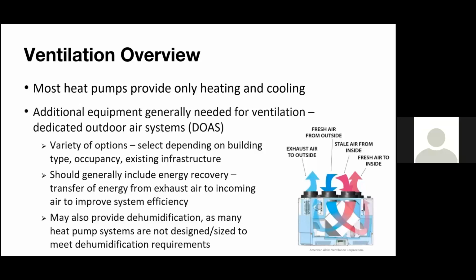So the second option, probably the first option, we'll forget about what I just mentioned there, is using an ERV with a static core. If you want some kind of energy transfer, you don't want to waste the heat that you put into a building, what you're able to do is bring in your outside air and mix it with your return air. So you could have 70 degrees as your return air. Let's just say worst case scenario, it's 0 degrees in Boston. We're mixing that together and you might get 35 to 40 degrees, right? And maybe if you did a little mixed air and brought that to the back of the fan coils, that would work. You might need to upsize your fan coils a little bit, your indoor units, but that could be a possibility. That's also worst case scenarios. You can get better: if we're at an outside temperature of 20 degrees, you might be getting 50, 55. So just something to think about there.